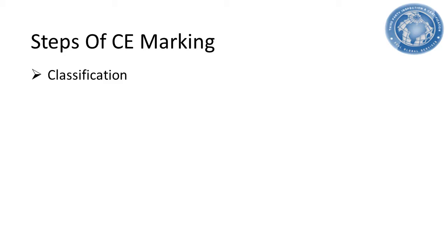First of all, you have to identify the classification of your products as per Annexure 9 of the Medical Device Directive. Along with that, you have to consider the amendment directives. You have to make sure whether your product needs notified body involvement in your CE certification process or not. If the notified body is involved, you have to identify the notified body and apply to them.